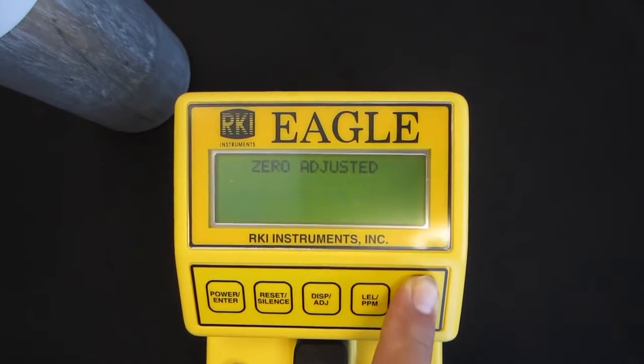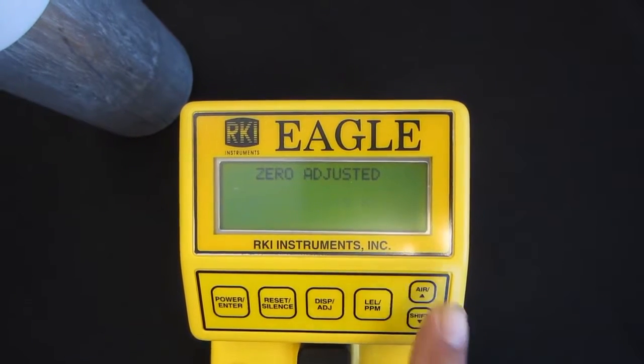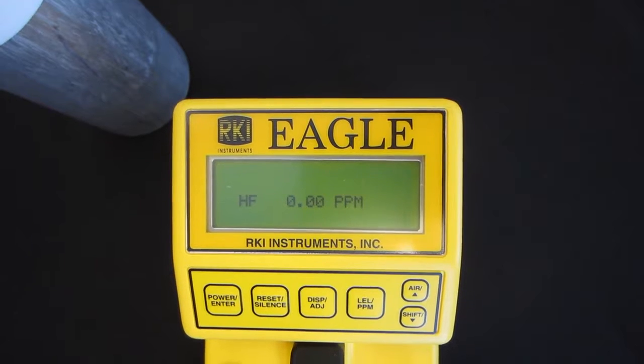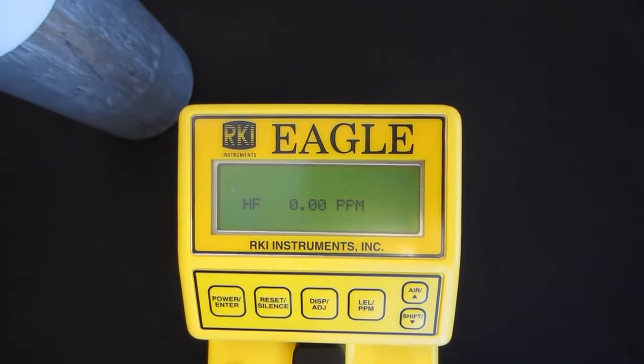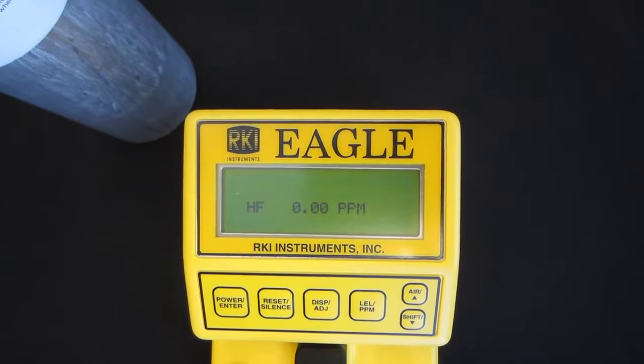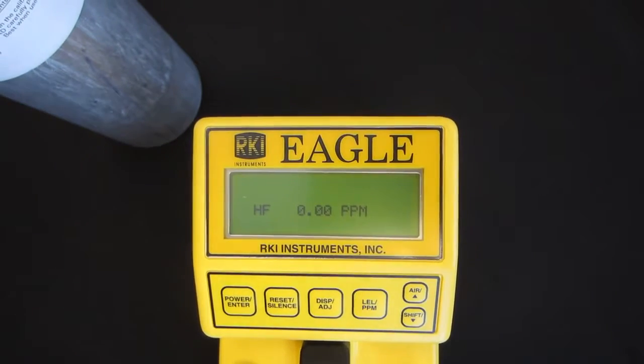And for zero adjusted, release the air key. So I'll release that, and again the unit's still reading 0, but at least we know we freshly zeroed the unit in a gas-free atmosphere before we apply gas to it.